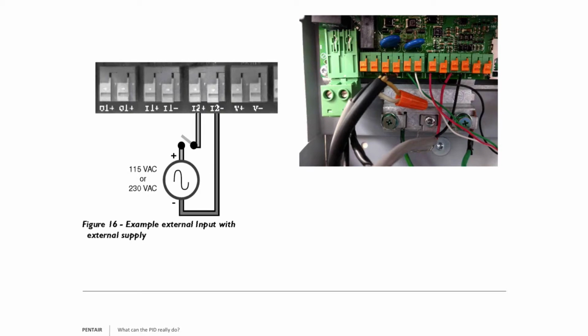Now, if in the case, for example, we want to hook up a secondary float, again, we want one that's normally open, one down, and when the float rises, it closes and passes voltage to the unit. And this is going to be my run command, for example, in a cistern. If we have a body of water that maybe a secondary pump pumps to fill, or maybe we have water delivered because we just can't develop a decent well, so we have a storage tank, I want the VFD to only run when there's water safely in the tank. Now, in the earlier picture, I just showed you the water sensor took up the input 1.